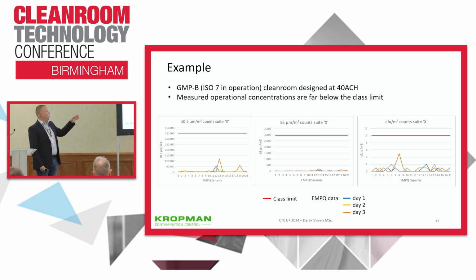Here you see the EMPQ results, 3-day measurements for a grade B clean room, ISO 7 in operation, initially designed at 40 air changes per hour. The clean room is fully occupied with 24 operators, and more than 20 measurement locations. What we see is that the measured concentrations, especially for the particles, are much lower than the class limit of grade B. This is not the only clean room in the Netherlands where we observe this big gap between class limit and measured concentrations, and for me it is the first indication that we over-design our systems. For CFUs it's a little bit different, but I will come back to that later.